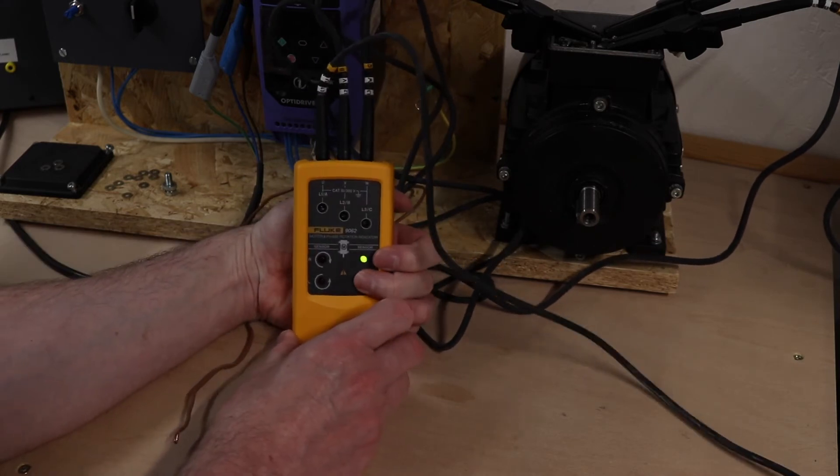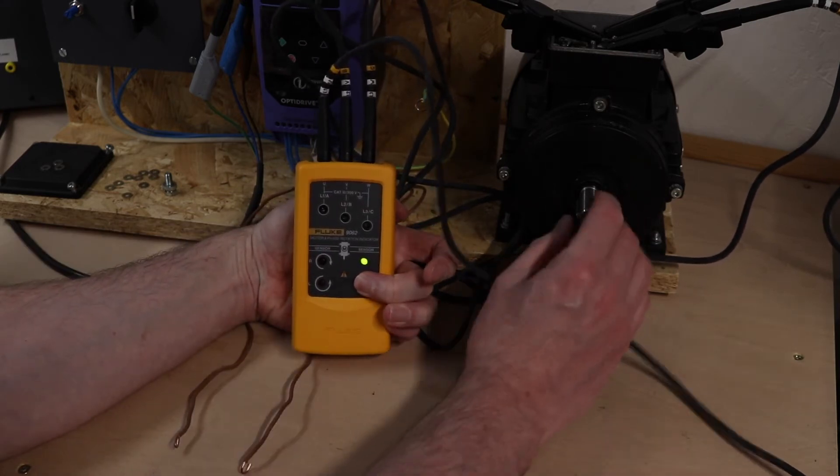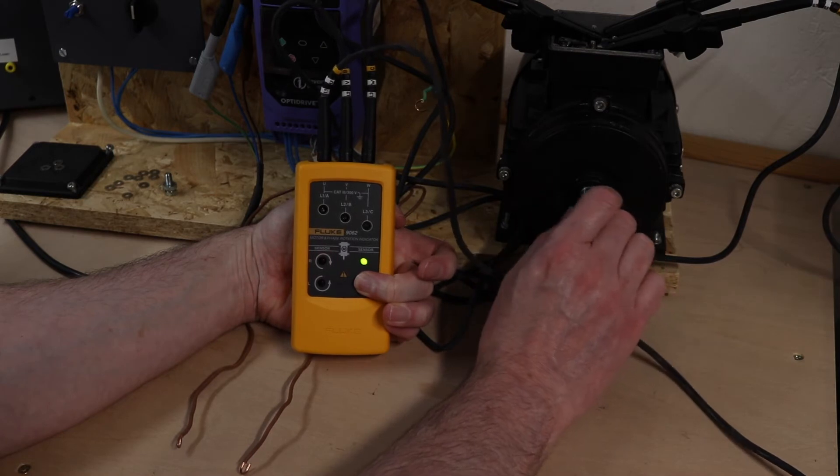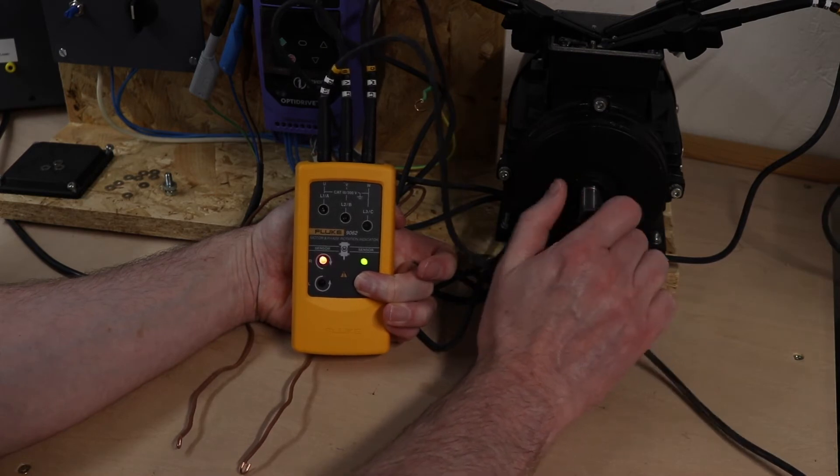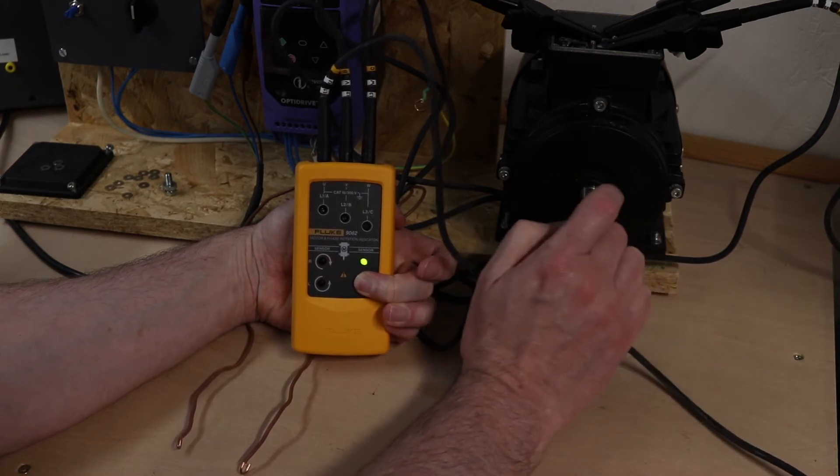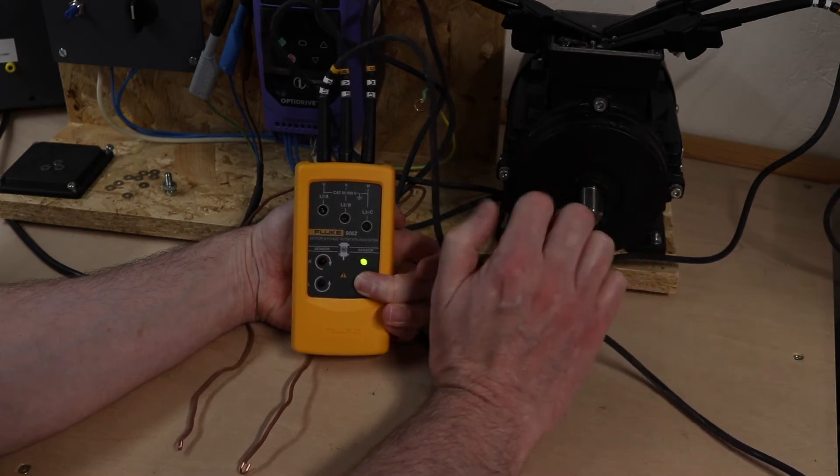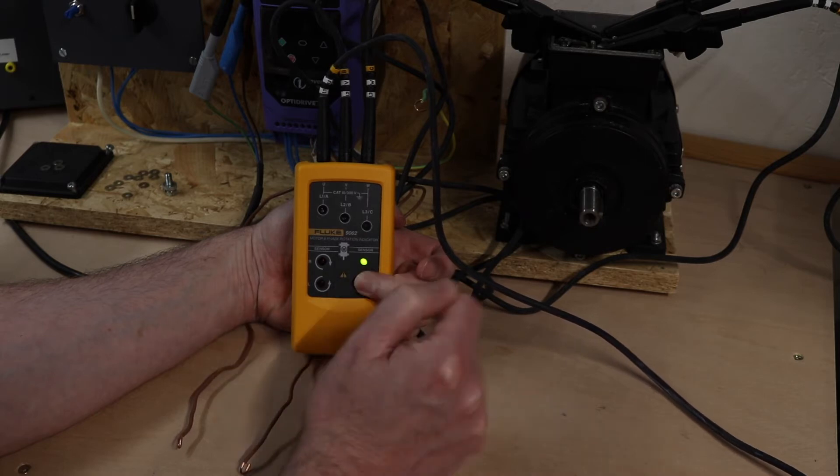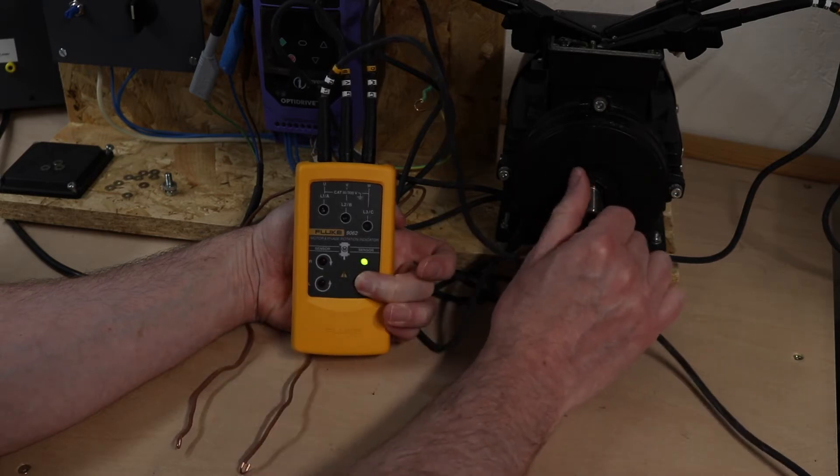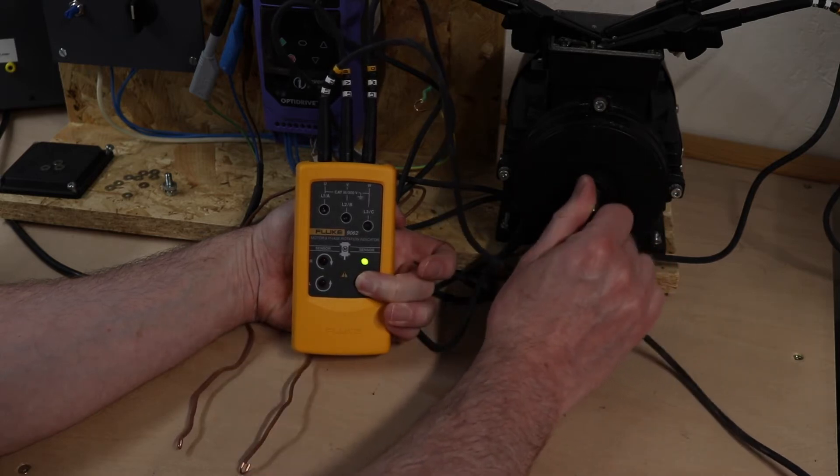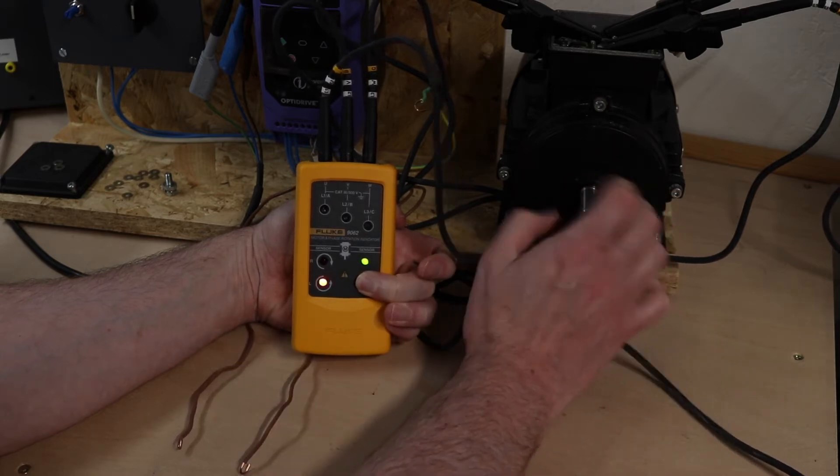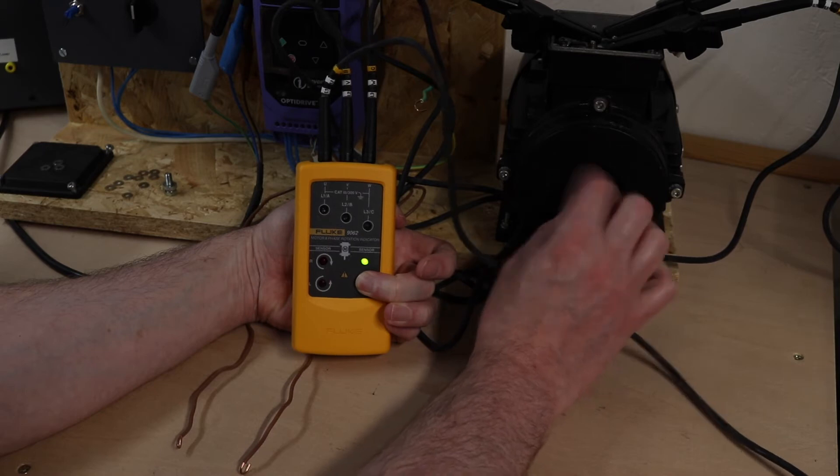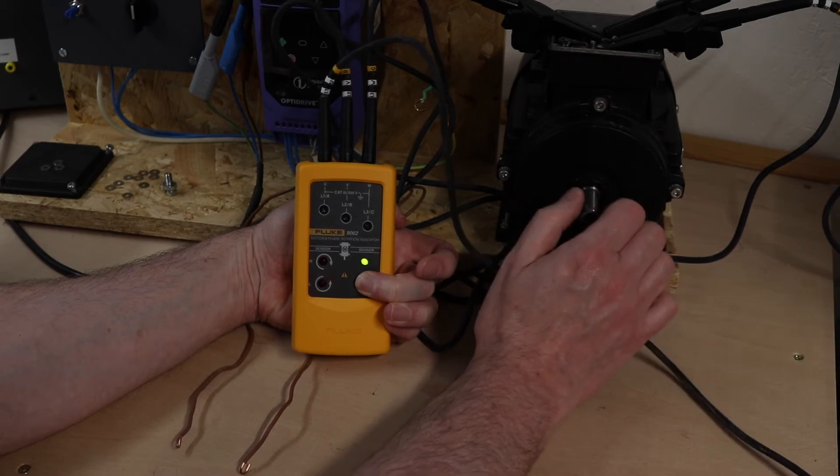Spin the motor and you can see for L1, L2, L3 connection I've got clockwise and if I spin it back the other way you can see it's flashing at anti-clock.